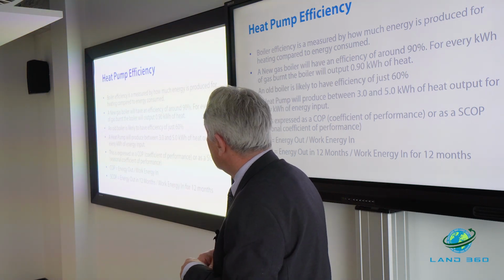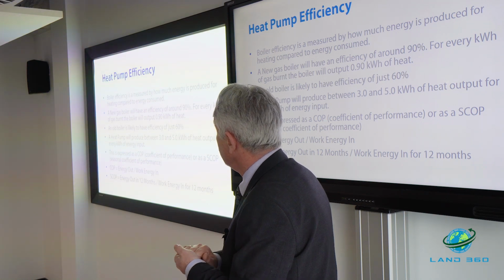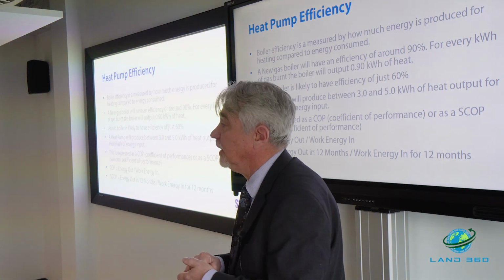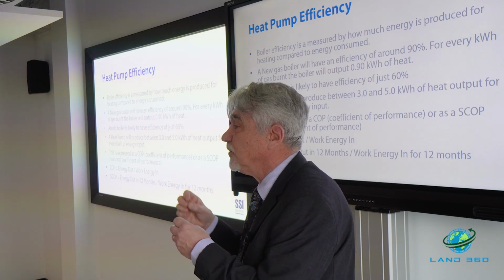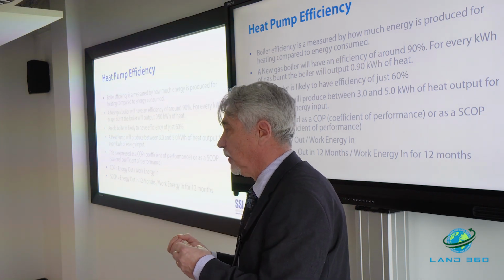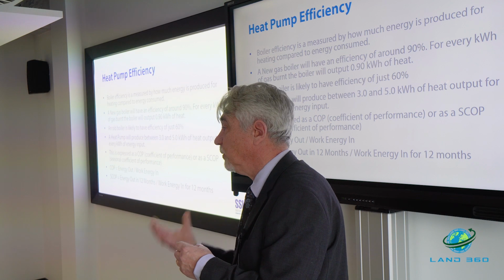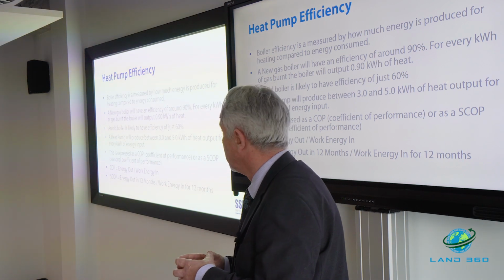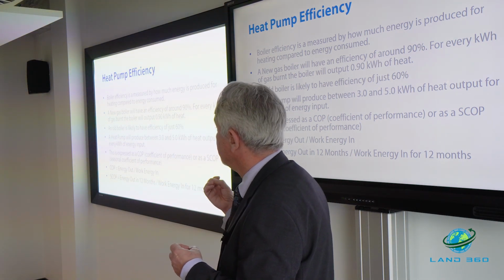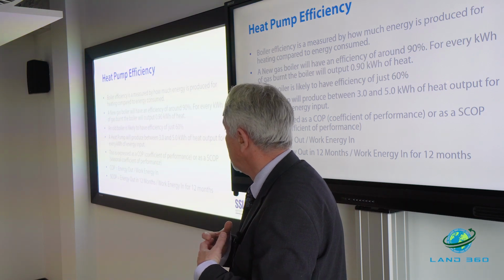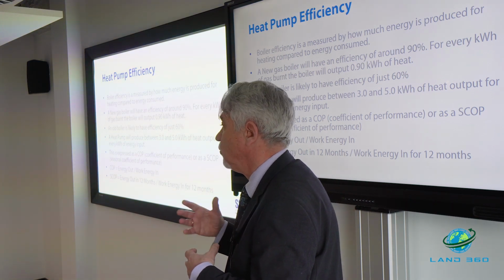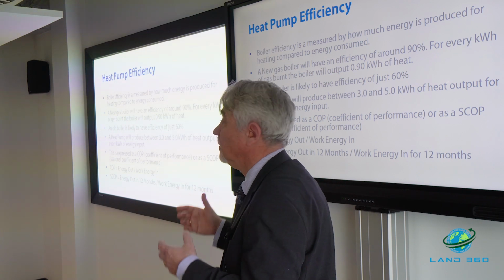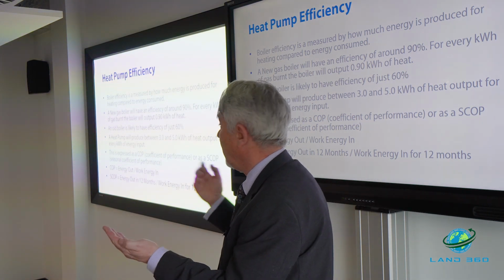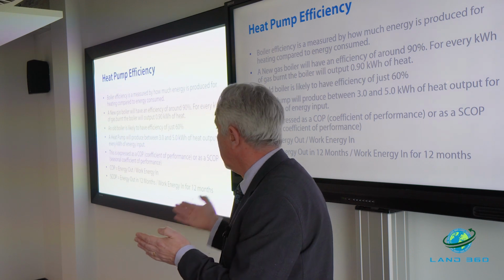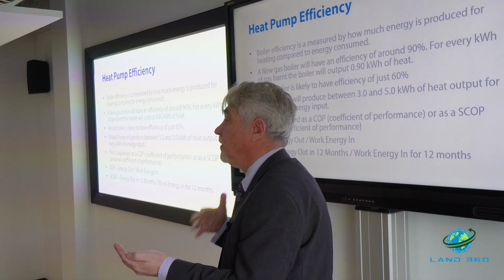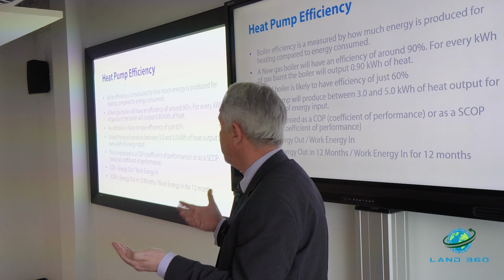Heat pump will produce between 3 and 5 kilowatts of heat output for every kilowatt of energy you put in. Again, that isn't free, it's coming from the ground, it's coming from solar again, from the heat that the sun is heating the ground up, we take that energy and utilise it. That's expressed as a COP, or a coefficient of performance, or an SCOP, which is a seasonal coefficient of performance. Coefficient of performance is energy out divided by energy in. With a seasonal one, it's energy out over 12 months divided by energy in over 12 months.